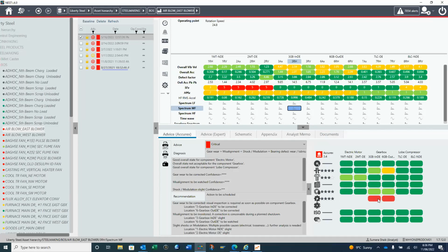There is gear wear and misalignment, because your bearing is going to fail. But not severe, but it's going to fail at some point. Not anytime soon, but still working maybe 2 to 3 months.